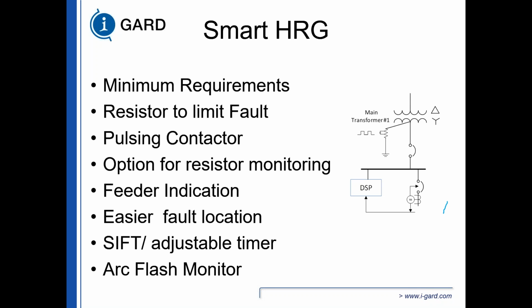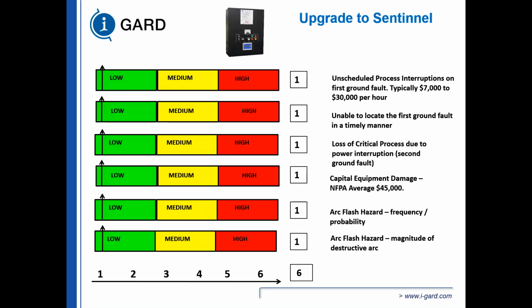So we developed an arc flash module that you can connect to your smart HRG system and interlock light, or have light only, or light and pressure to trip the main breaker should you have an arc flash, giving you the ability to both lower the probability of having an arc flash as well as lowering the magnitude of the arc flash. So our risk meter now looks like this. Unscheduled process interruptions, 1.